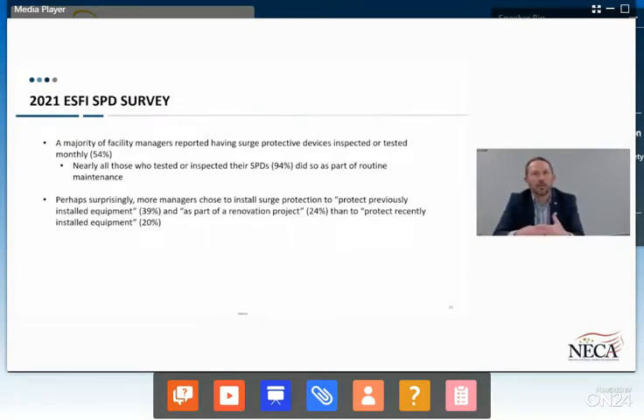So each PM for a surge protector is going to be unique to the situation you're in. If you're in a critical asset, say a substation for a utility, protecting some sensitive equipment in there, well that's going to be a lot different than someone protecting their gaming system at their house. The point is common sense applies a lot to this.